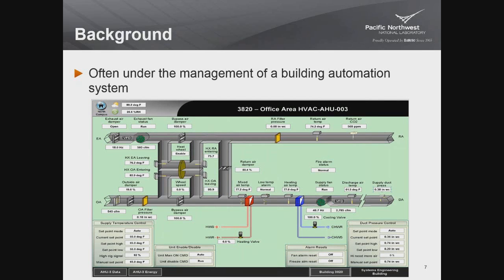They're often under the management of a building automation system, especially for large buildings, not necessarily for smaller buildings. This is a screenshot from a building automation system, the computer workstation. It shows the status of an air handler, a VAV air handler, and all the different control points, things that are controlled: energy recovery wheels, fans, dampers. Just an example of what that would look like.